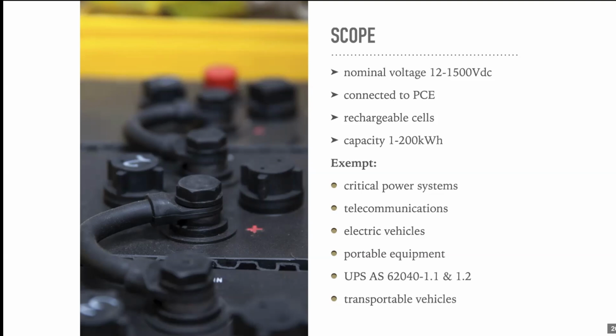It has to be a battery system that's connected to power conditioning equipment. I'm not sure why you would have a battery doing nothing, because if you don't use it for any purpose at all... Power conditioning equipment by definition is anything that modifies voltage, frequency, power, or current, sorry. As a result, if you connect a charge controller, an inverter, or even a load that runs off a battery that modifies it in any way, it is now power conditioning equipment. Connected to rechargeable cells, not primary cells. A primary cell is not rechargeable, so it's just a disposable cell. And capacities of 1 to 200 kilowatt hours.